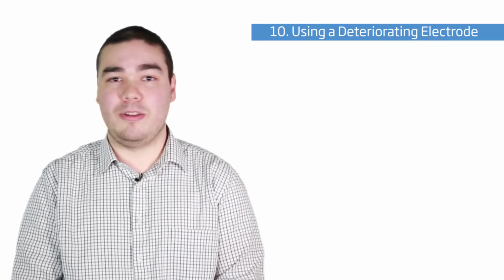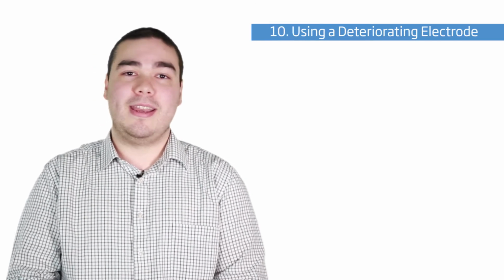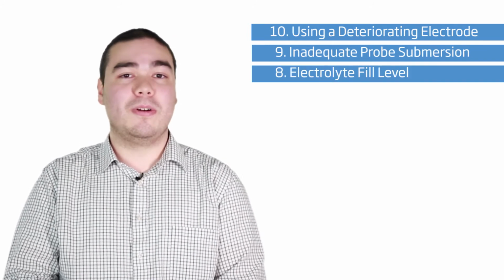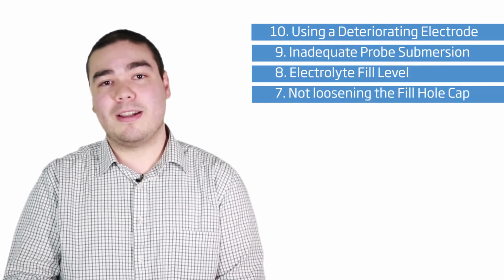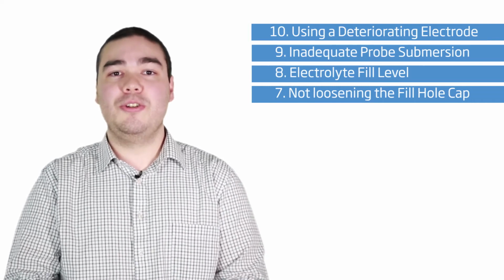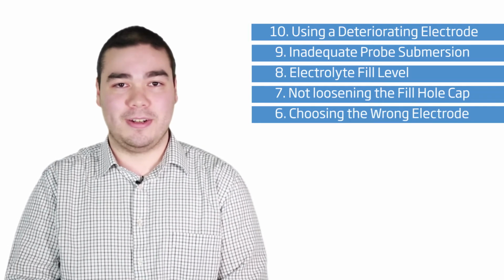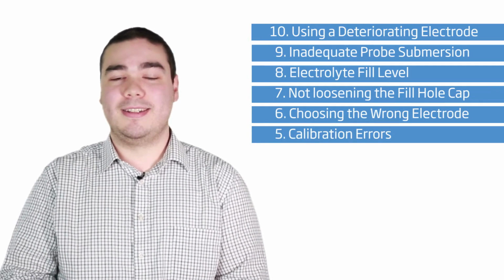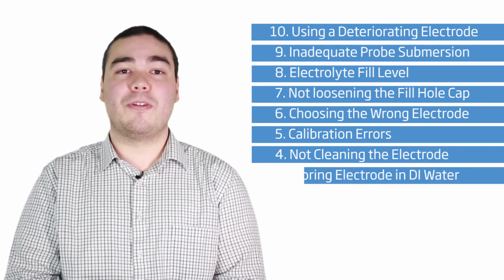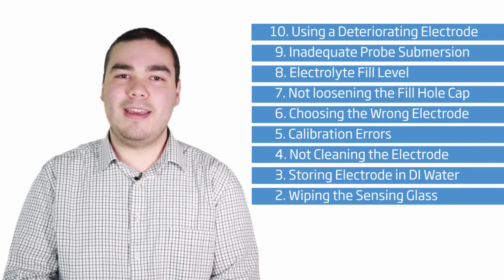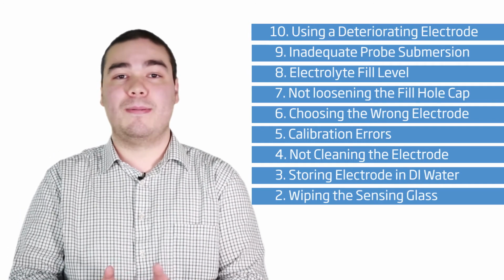Well, we've come a long way to get here. To recap, we discussed using a deteriorating electrode, inadequate probe submersion, low electrolyte fill levels, not loosening the fill hole cap, choosing the wrong electrode for your application, calibration errors, not cleaning the electrode, storing electrodes in pure distilled water, and wiping the sensing glass. These 9 mistakes happen to someone, somewhere, every day. Number 1 is no different, and it happens more often than you might think.